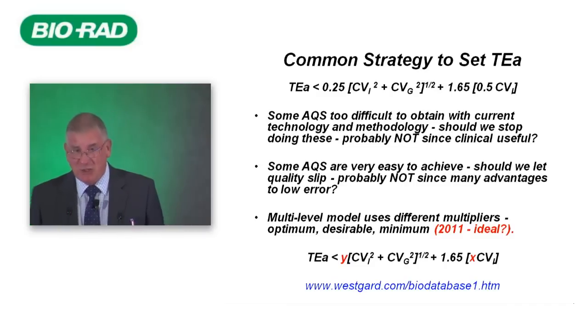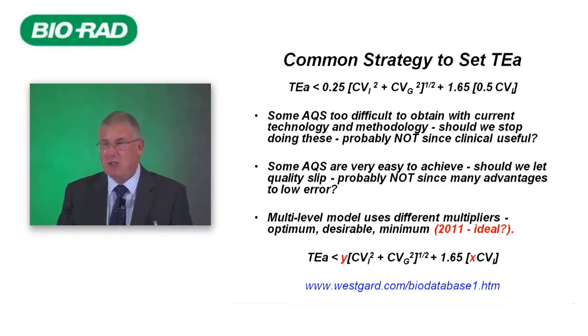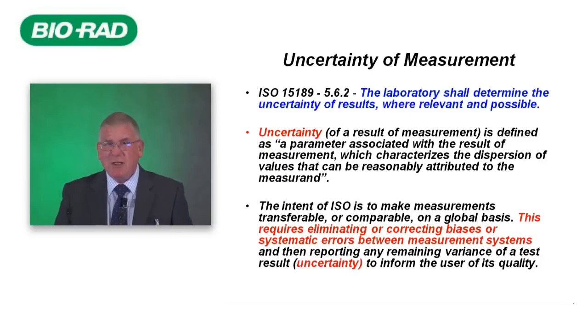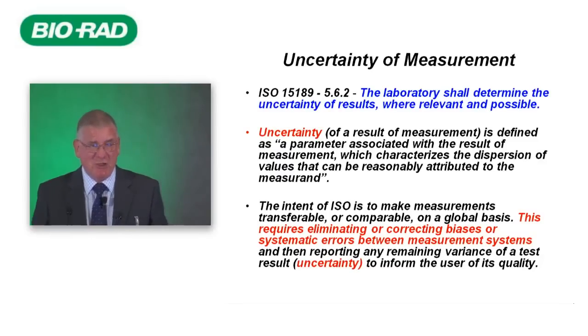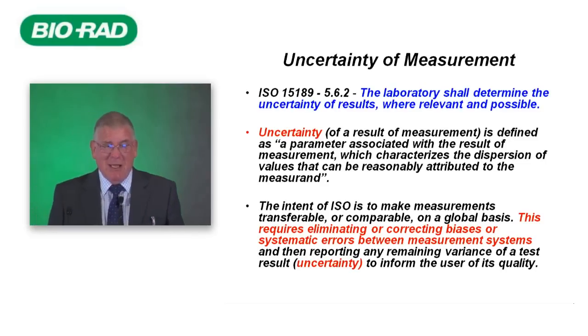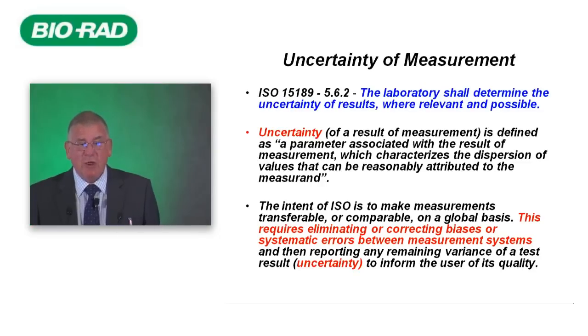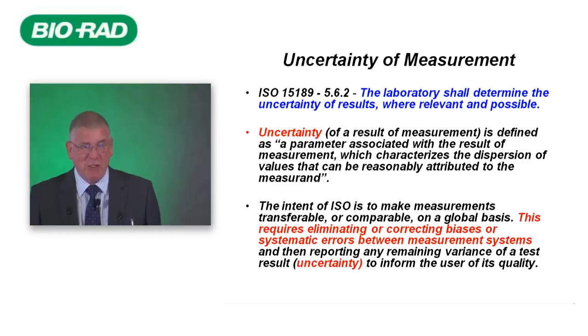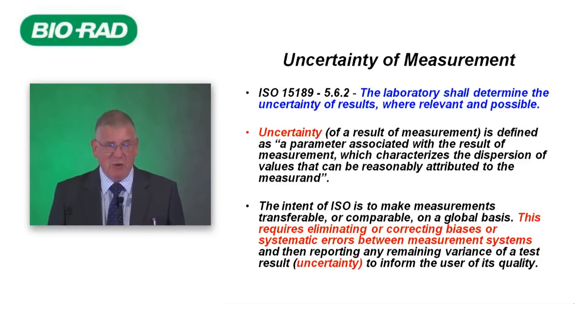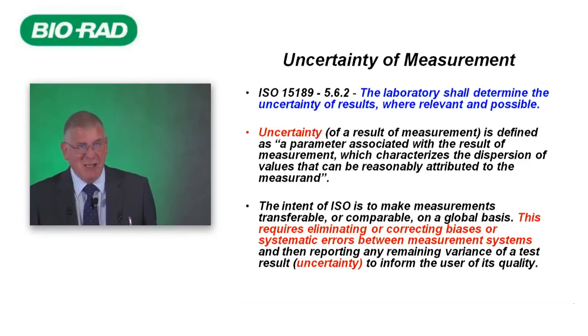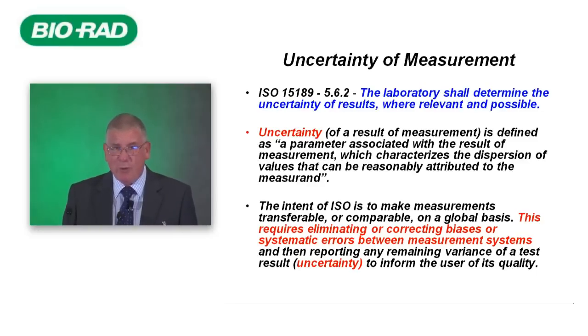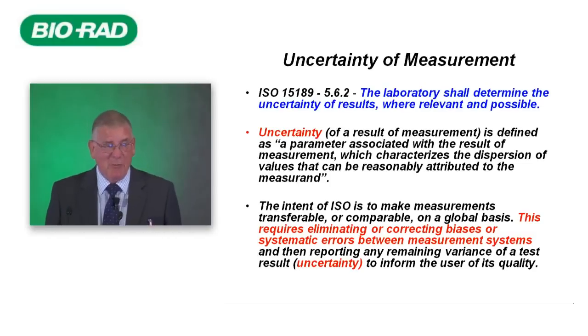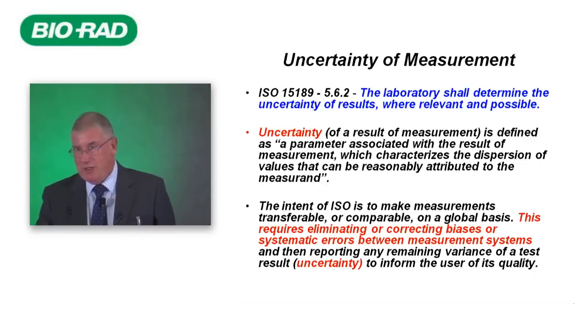At our 2011 convention, as you'll see in the preprint in your packs, we suggested there might be an ideal — a fourth level of analytical quality specifications based upon biology. Now let's turn to measurement uncertainty. ISO 15189 states clearly: the laboratory shall determine the uncertainty of results where relevant and possible. The definition: a parameter associated with the results of measurement which characterises the dispersion of values that can be reasonably attributed to the measurand. The intent of ISO is to make measurements transferable or comparable over time and geography, requiring elimination or correction of biases.